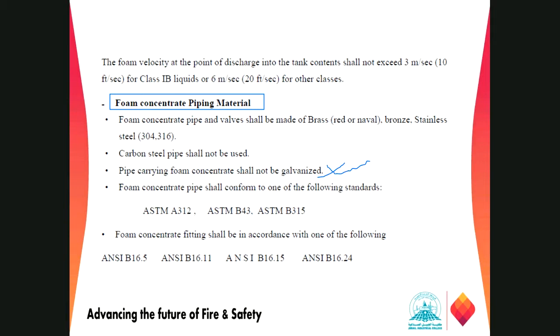We have to use only corrosion resistant material because the concentrate is highly corrosive in its raw form. I mean, when it is stored as a concentrate like 3%, 6%, and so on, we have to be careful regarding that.